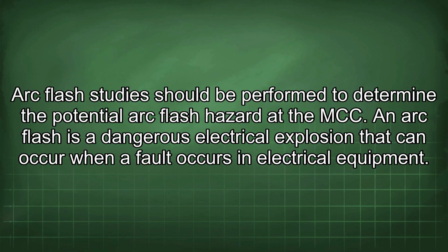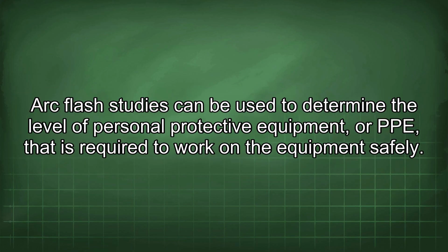Arc flash studies should be performed to determine the potential arc flash hazard at the MCC. An arc flash is a dangerous electrical explosion that can occur when a fault occurs in electrical equipment. Arc flash studies can be used to determine the level of personal protective equipment, or PPE, that is required to work on the equipment safely.